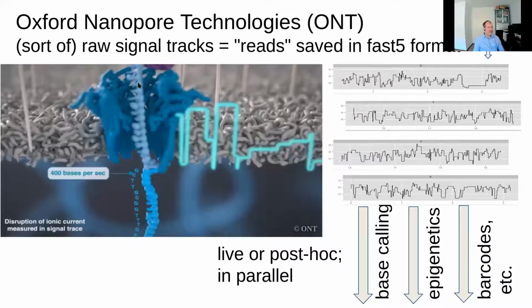Nanopore sequencing is dragging a DNA strand, typically a single strand of DNA, through a proteinaceous pore molecule, and looking at the ionic current that can still pass besides the molecule. So it's in fact a molecular Coulter counter or hematocytometer-like device that works with many parallel channels.